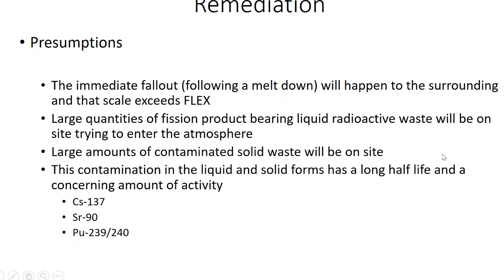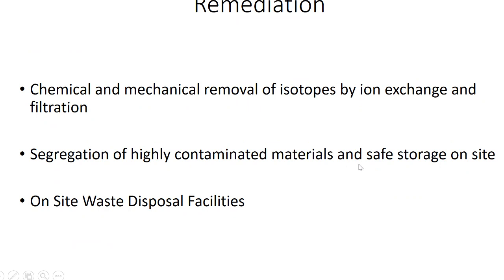There are solutions to that, fortunately. Waste ROs and ion exchangers function very well, and what we need to try to remove here is our long-term fission products: cesium, strontium, and your transuranics. We discussed using an ion exchanger. Anything we use, your pump trucks, your portable pumps, are going to wind up being highly contaminated at the end of the day, and you're not necessarily going to have a good place to put those. So we can start looking at, can we build an on-site waste disposal facility? Maybe it's a mausoleum, maybe it's someplace in the ground.